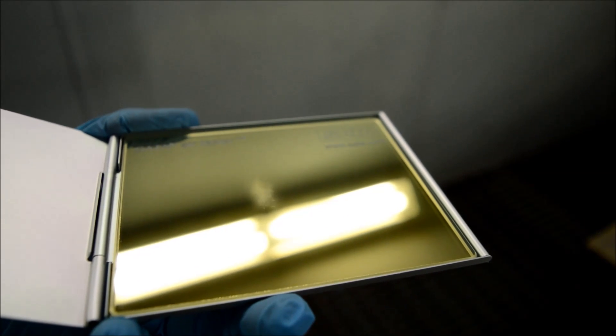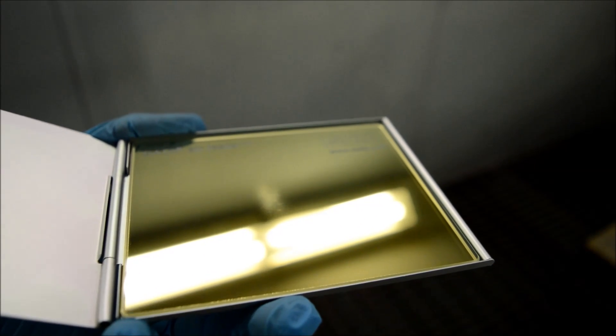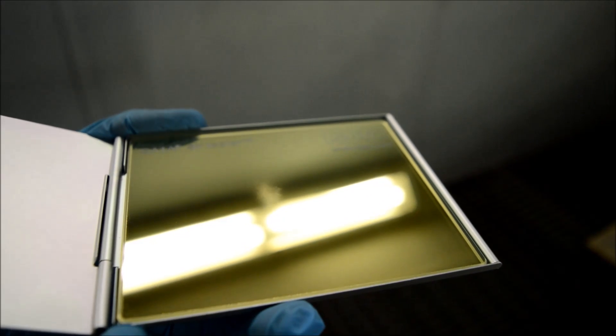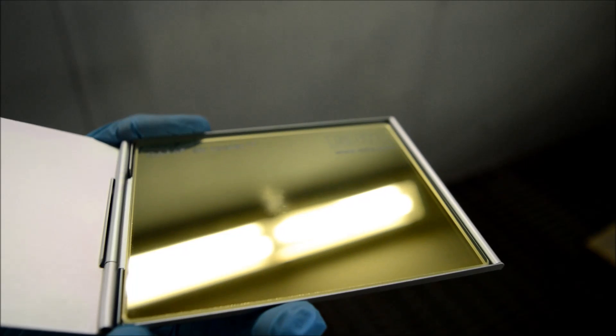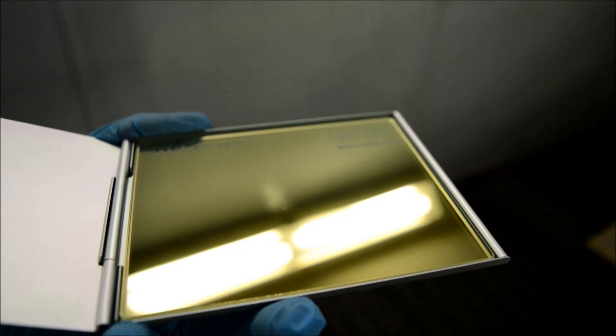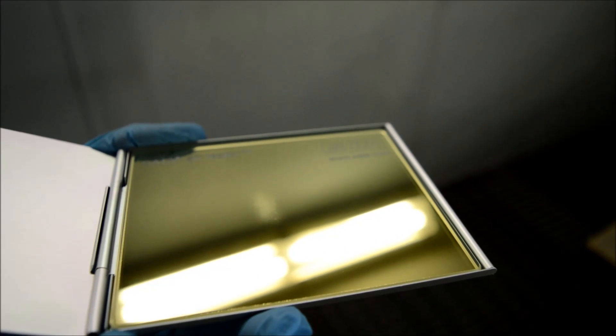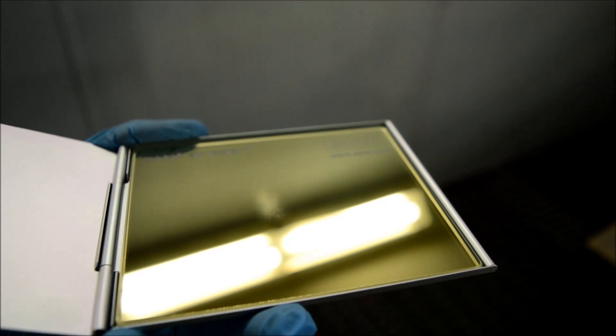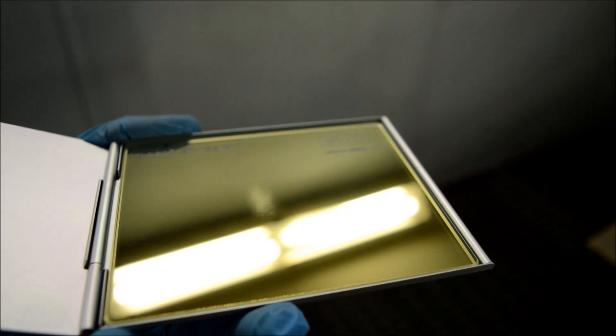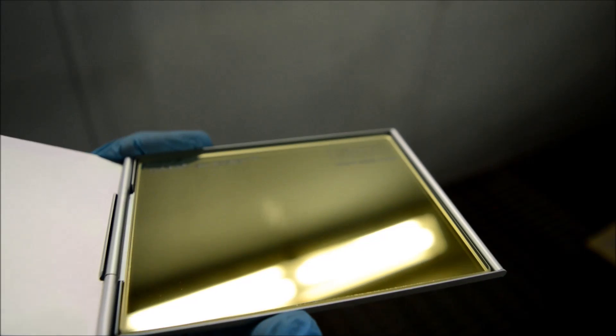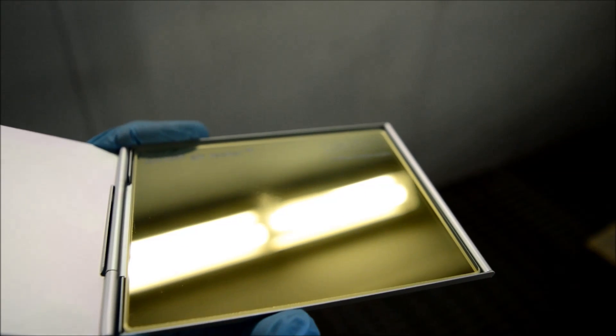Just by looking at this, we can tell there's some form of oils or water going through our airlines. We now know we need to look at our filters to make sure they've been regularly serviced, check when they were last serviced, and it's looking like we'll need to replace some filters to get rid of this contamination.